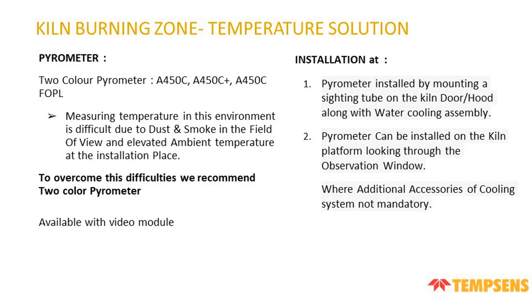Kiln burning zone temperature solution: pyrometer. We use the two color pyrometers A450C, A450C+ and A450C FOPL to measure the temperature in the kiln burning zone. This pyrometer is used because the kiln is very dusty and smoky in the field of view and has an elevated ambient temperature at the installation place. To overcome this difficulty, we recommend the two color pyrometer. Two color pyrometers come with two types of sighting options, through the lens sighting and laser sighting. We have an option available for the Plus series, special for the video module.